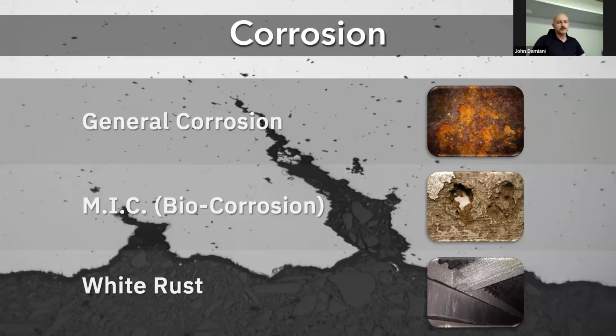White rust is specific to galvanized steel, and it's something we always talk about with cooling towers, because a lot of galvanized metallurgy exists in the industry, from entire galvanized towers to towers with a stainless basin but a galvanized shell. Any galvanized metal present, we need to take measures to protect the zinc coating, because it's very susceptible to corrosion under the wrong conditions.